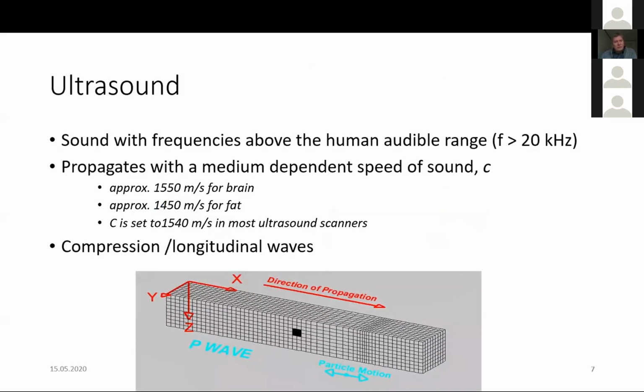Ultrasound is sound with frequencies above the human audible range, so above 20 kilohertz. In medical ultrasound imaging, frequencies between 2 megahertz and perhaps 20 megahertz are usually used. The speed of sound is different in different media. The speed of sound in air, for example, is a lot lower than the speed of sound in brain. But also among tissues, you may have differences in the sound velocity. It's also good to know that sound propagates as compressional or longitudinal waves. So it's a pressure pulse propagating in the medium. It doesn't propagate like ocean waves.